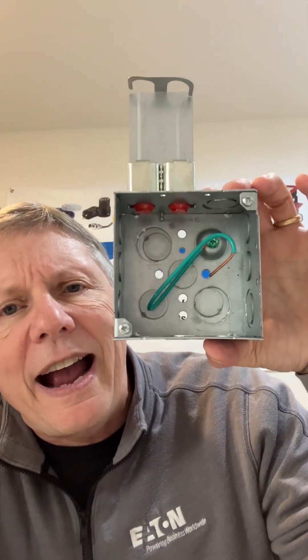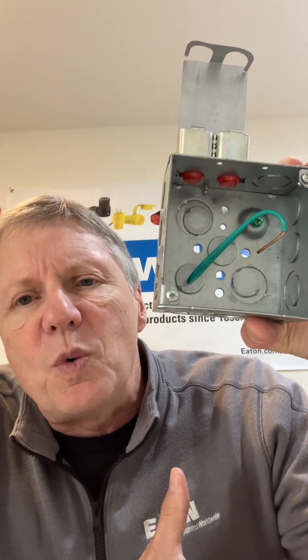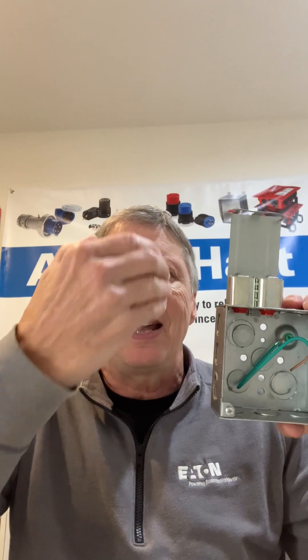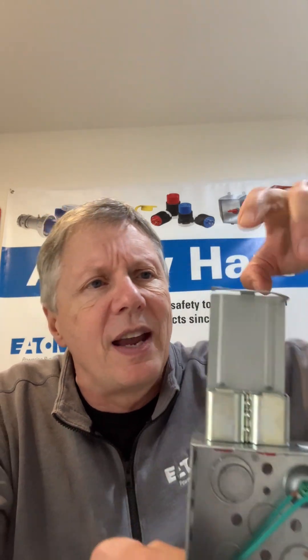When you look at the Crouse-Hinds side, they have something called a quick lock outlet box, which comes from the factory like this. They have a distinctive S-curve design, so you can mount them next to each other on a steel stud. You'll also notice they have what I call a quick connect for MC that's already installed in the box, and then you've got your cable management system. When you go to wire this up, all you do is feed the MC right through, click it in, and it's already installed — so it's going to look something like this right here.